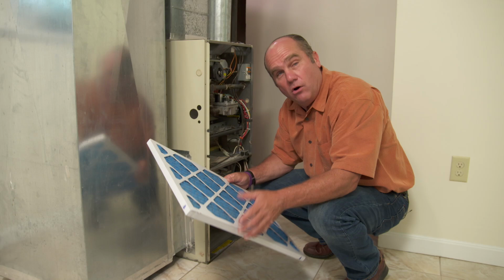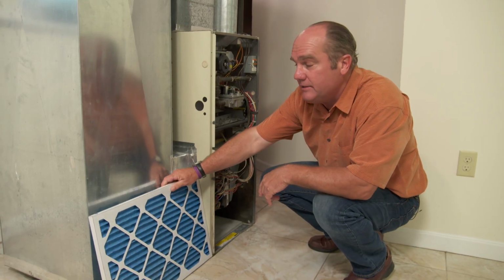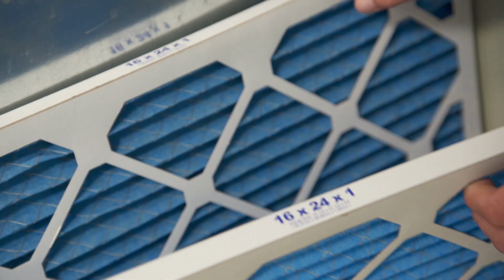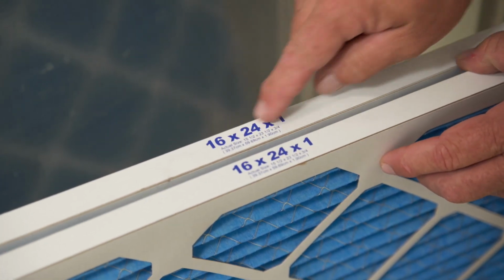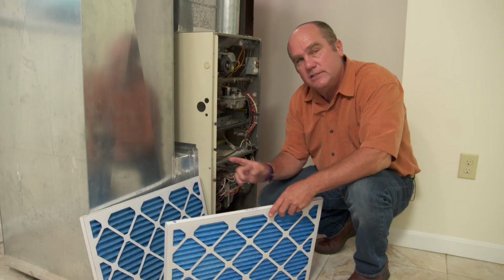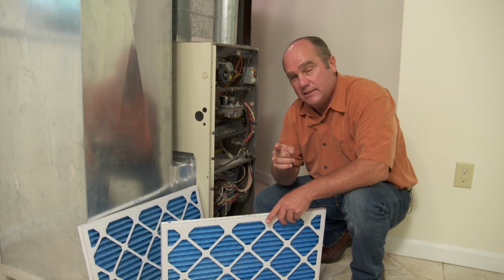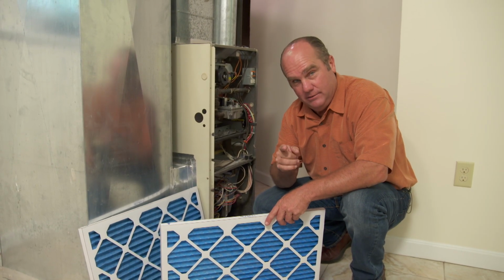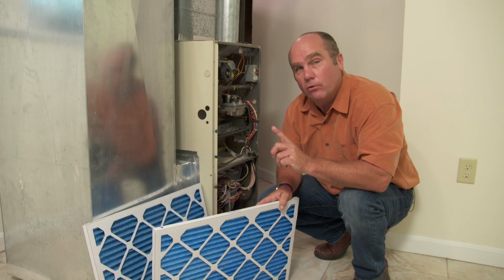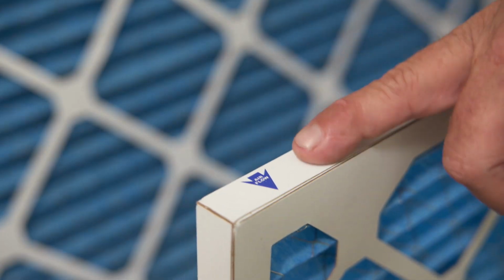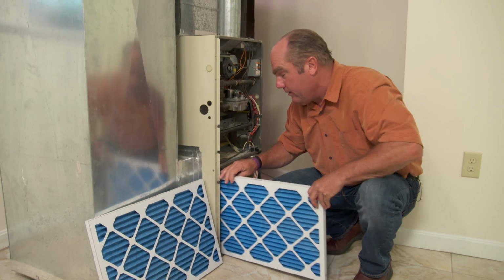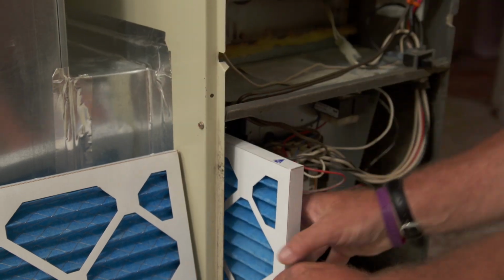Replacing a filter is something the homeowner can do. You need to get the exact replacement filter. The nice thing is they are labeled so you can see the size you need. You want to change these filters at least once per season, and more if you've got pets. Now, you also want the filter to be oriented in the right direction. You can see an arrow right here indicating that the air will return this way.